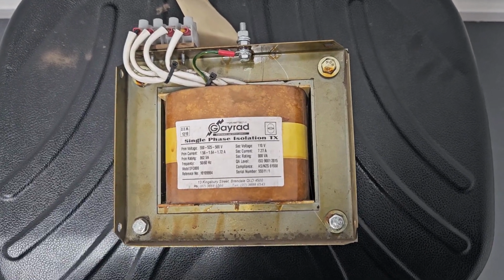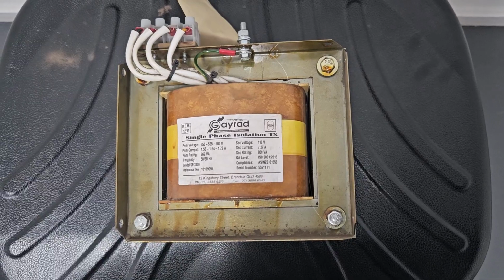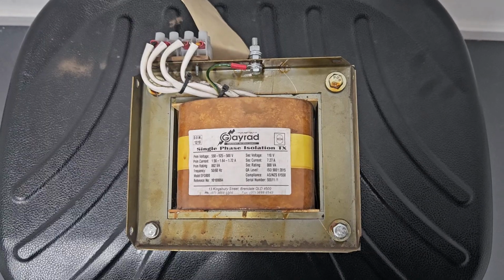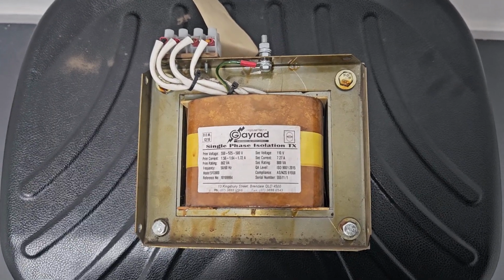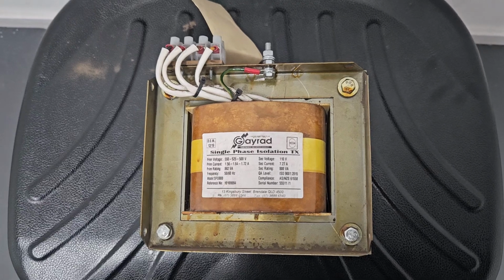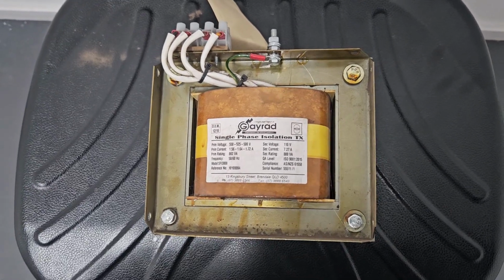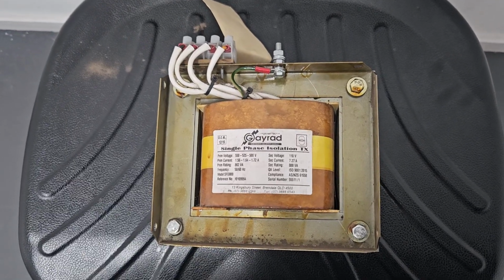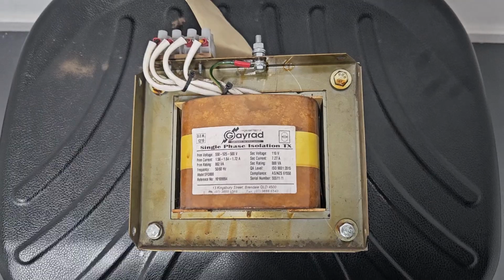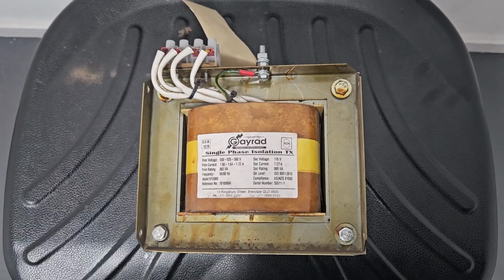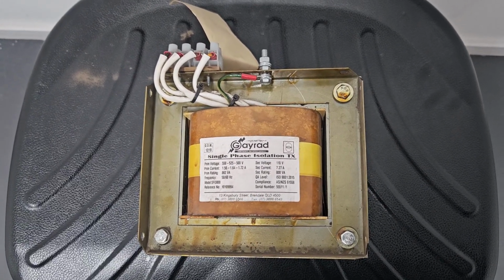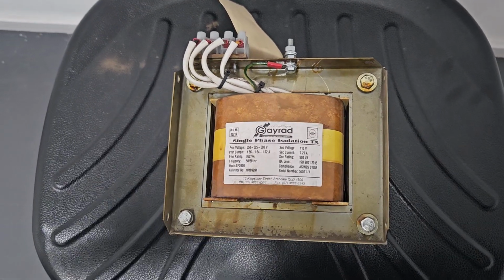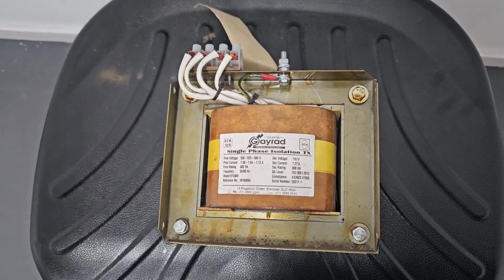Okay, so you'll find a lot of transformers, like I said in the beginning, starting from generation. Most of the time when electricity is generated at a power station, it's generated at a smaller voltage, say maybe 11 kilovolts as an example. And then it's transformed to a higher voltage using this device, the transformer, to about 132 kilovolts, in some cases even as high as 400 kilovolts. And then it gets transmitted to the users.